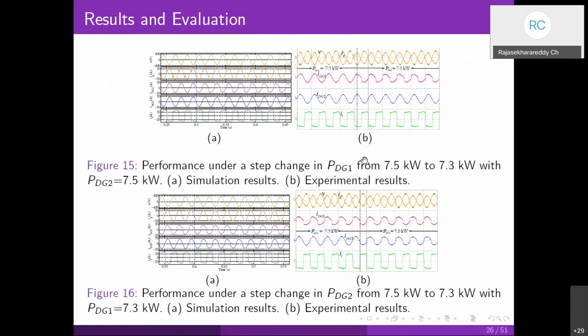Then here we have results showing coordinated control of two DG inverters. We have DG1 and DG2. This orange line is the grid current, and this yellow line is the grid voltage. When both the inverters are fully loaded with active power generation, they are not providing any harmonic and reactive currents compensation, so their waveforms are seen to be sinusoidal.